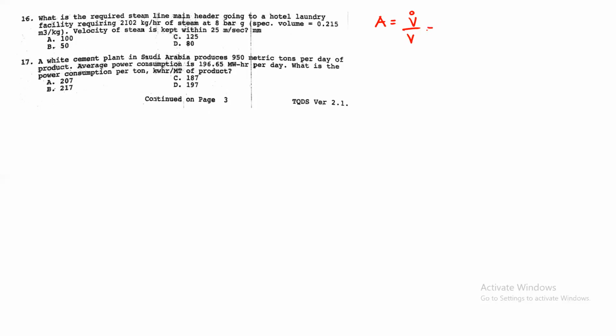So si volume flow rate pwede natin makuha using mass times specific volume. So ilan yung mass natin dito? 2102 kilograms per hour. So convert times specific volume na 0.215 meter cube per kilogram. So maka-cancel si kilogram. Then i-convert natin, so times 1 hour per 3,600 seconds. So divided by velocity na 25 meters per second. So maka-cancel dito yung second. Maka-cancel dito meter. Then ito magiging squared na lang. So ilan tong area natin?